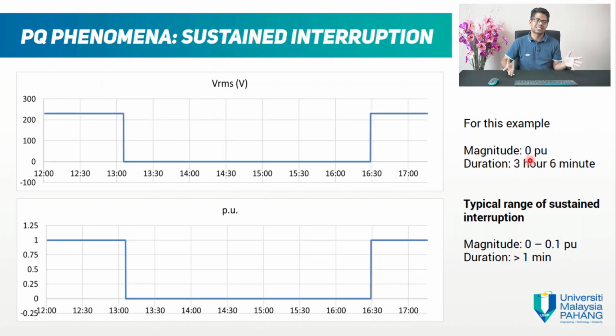And this is the typical thing that you call a blackout, but it lasts longer than 1 minute. For this example, it starts slightly after 1 o'clock and finishes at 4:30. So it's 3 hours and 6 minutes at 0 pu. No voltage at all. This is the typical magnitude of 0 to 0.1 pu when the duration is more than 1 minute. That's sustained interruption.